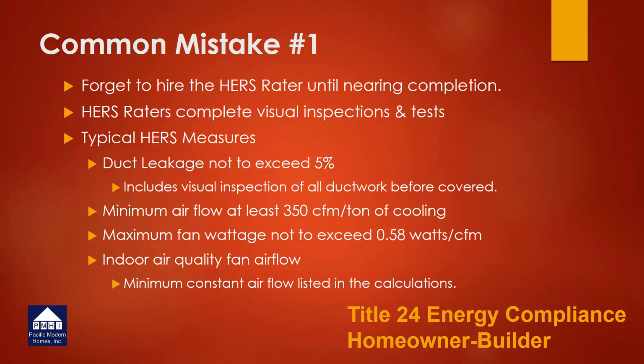Typically, the HERS rater needs to come out and inspect the ductwork before any sheetrock goes up. They'll also need to do their duct testing, and they'll need to test for minimum airflow and for fan wattage. You want to get those tests done as soon as you can in the process so that if corrective measures have to be done, you're not having to tear out sheetrock or other items in order to get them into compliance. Also bear in mind the exhaust fan in the bathroom, or multiples. If you decide to use multiple exhaust fans to meet the air quality requirements, those have to be tested by the HERS rater to verify that they don't use too much energy and that they're providing the minimum air quality flow.